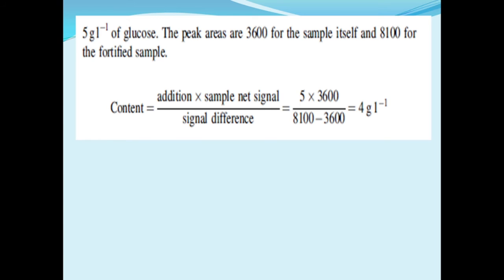In the case of internal standard calibration, this is not necessary and small variations in injection volume cease to be important. If sample preparation is complicated or demanding, the internal standard approach is strongly recommended. In this case, the standard is added before the first preparation step has begun.